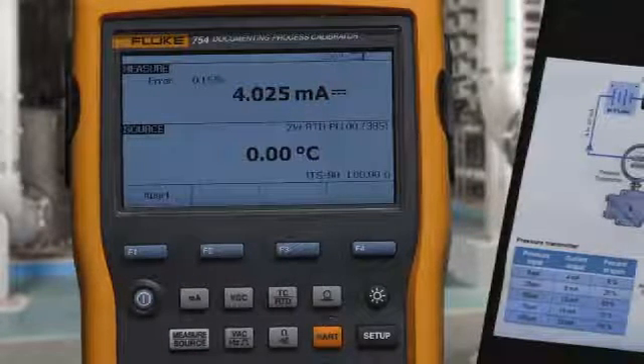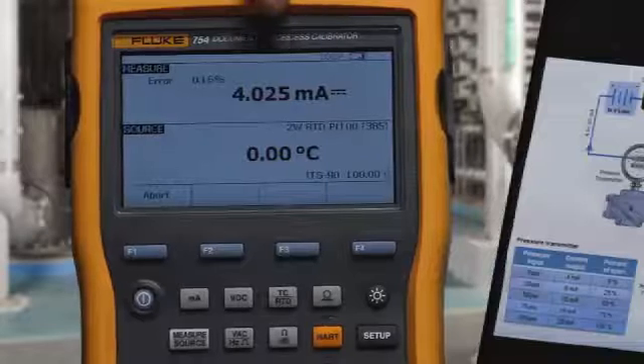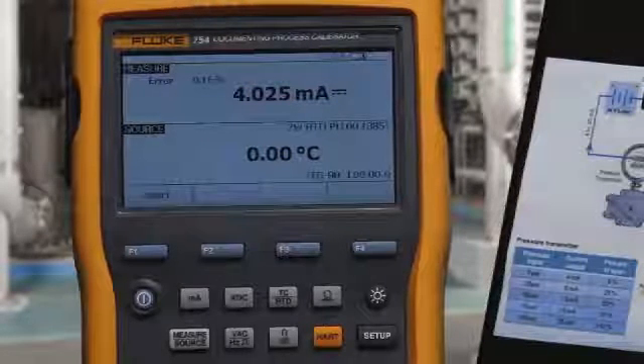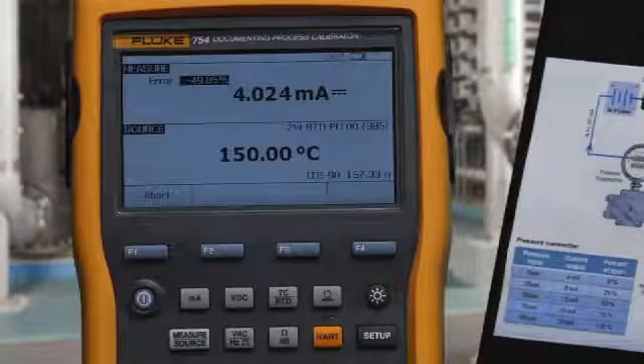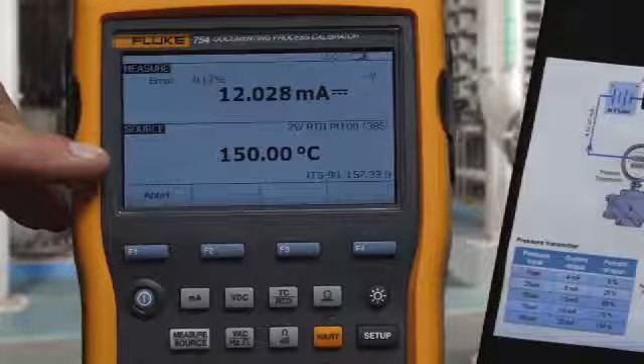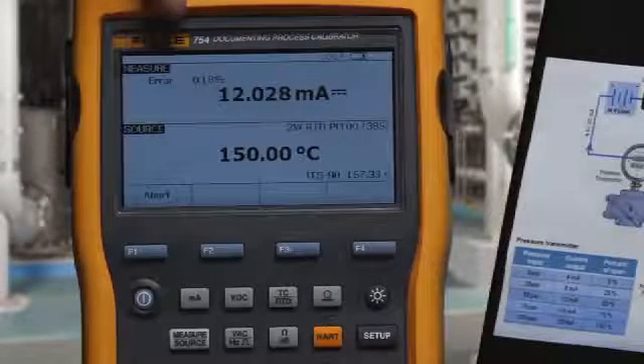0 percent, 4 milliamps is being measured, error percent is being calculated. The 50 percent value is applied, milliamp measured, and error percent being calculated.